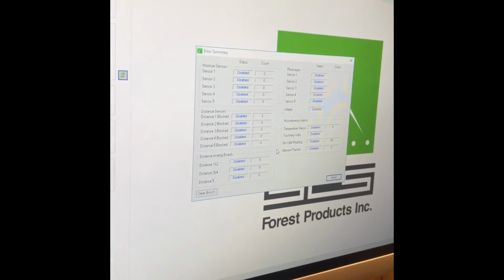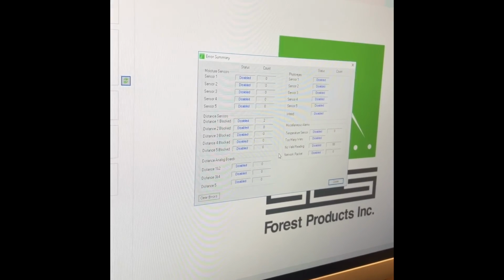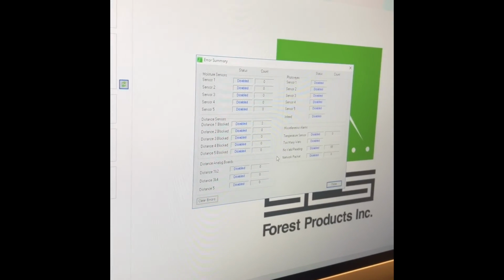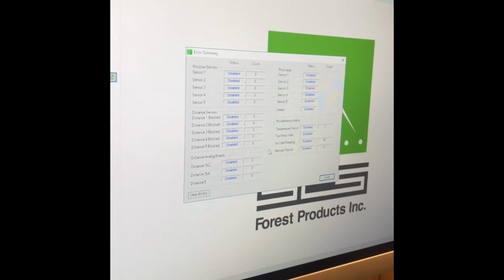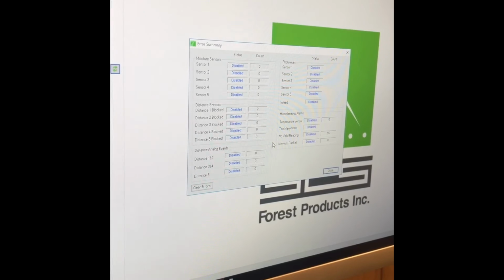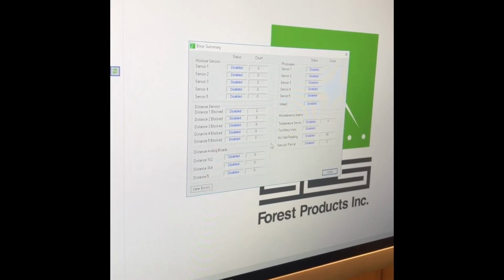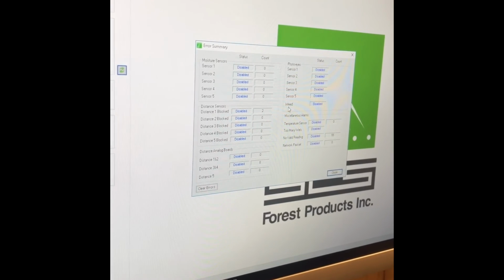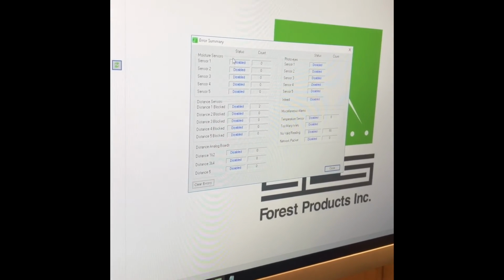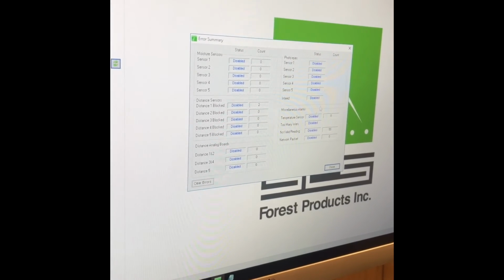Errors. The alarms are disabled because they're not going anywhere. I disabled them too because it could start making the system act a little bit erratic. But if you guys do decide, we have 2 alarms for various outputs. So you have way more options on what can trigger the alarm, but you only have 2 alarms. And we'll go over that as well. What you're looking for primarily here is sensors being blocked. That would indicate that they're dirty.